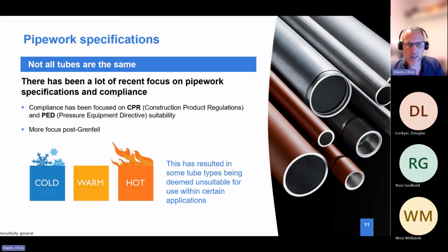Recently we've seen changes in legislation, particularly around what we call cold form tube, which means it's no longer suitable under the PED, and has always only technically been suitable for temperatures up to 50 degrees C. So it's fine for chilled water systems, but if you're using it for high temperature hot water systems, then technically it's the wrong product to use.